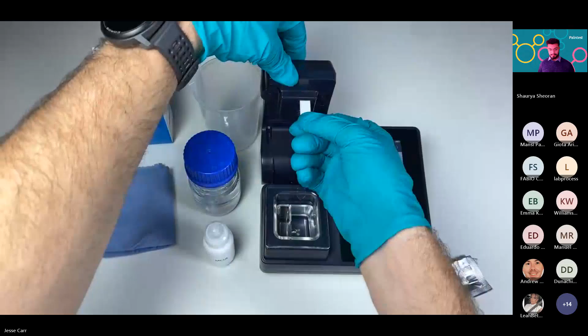So remove our sensor, discard our sample, and then if we want to do best practice, we can open up the device and just wipe down these electrodes to make sure they stay nice and dry and they don't corrode or anything. And you can close the device and that's it.